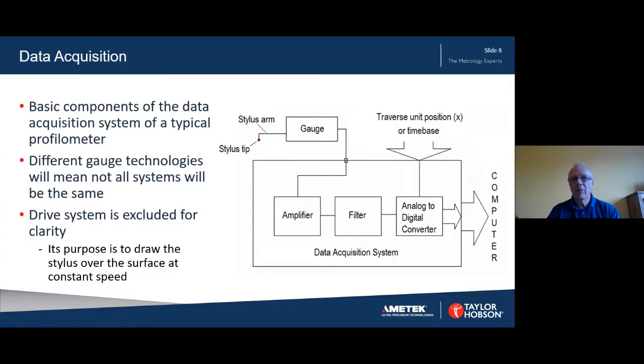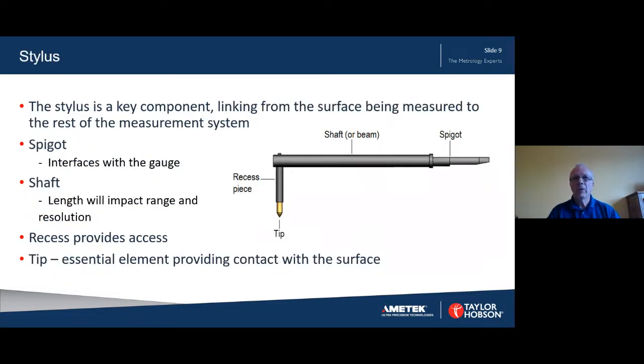This schematic shows the basic building blocks from the stylus tip through to the computer used for analysing the data. There will be differences between different systems that employ different gauging technologies. These components are the critical path in the measurement of surface texture. One of the key components of the system is the stylus, which can be tailored to a given application by altering the length of the beam or the length of the recess piece to gain access to critical features on the surface. The length of the shaft will have an impact on the fundamental range and resolution of the instrument.